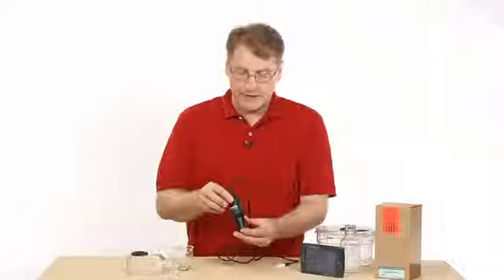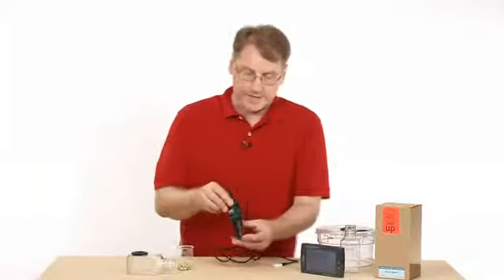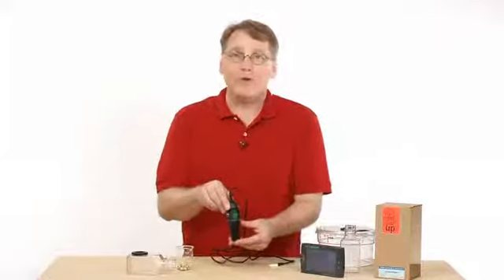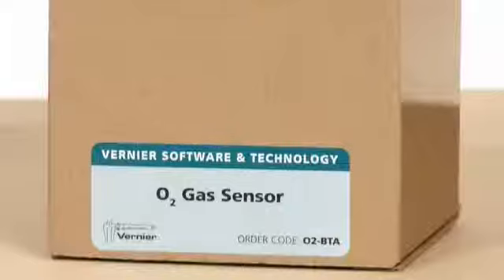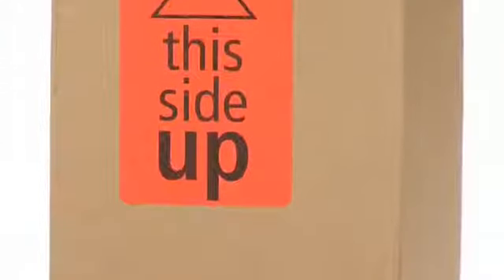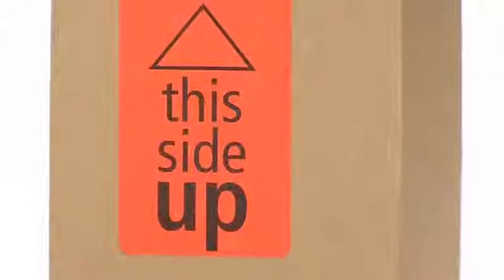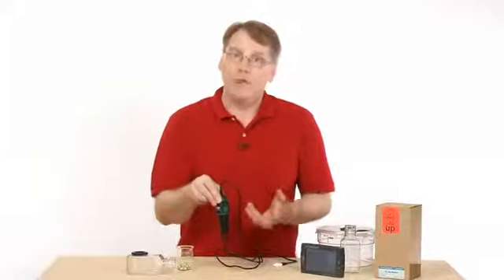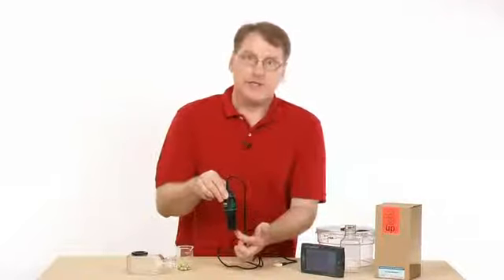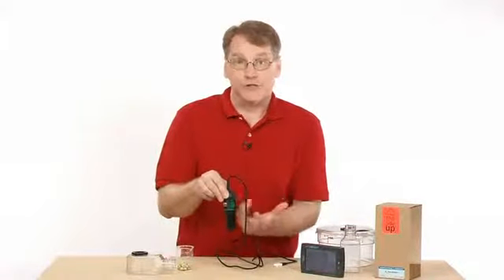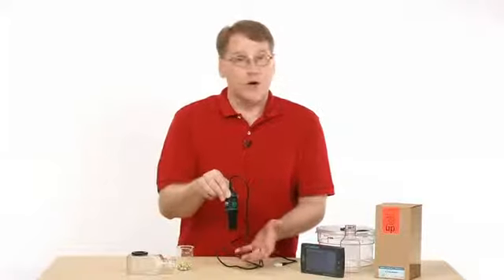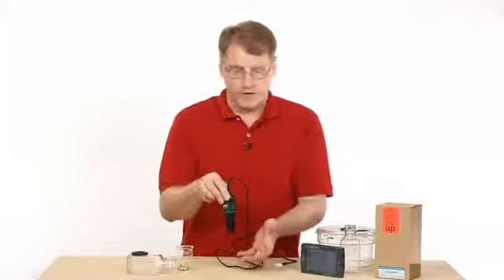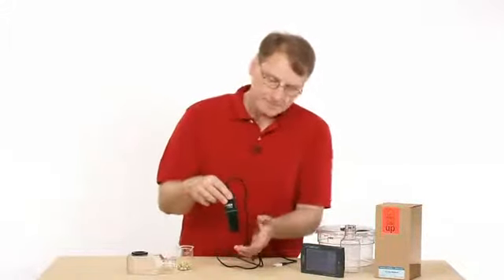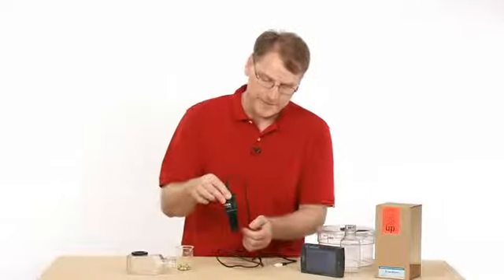One thing about this sensor is that you need to store it vertically. It comes in this box that says this side up, and the sensor is in the box in that orientation. And it's important that you do store it that way. The membrane down here, there's a gel that needs to stay across the membrane. Otherwise, you could damage it if you stored it for long term on its side there. So it's important to be able to do that.